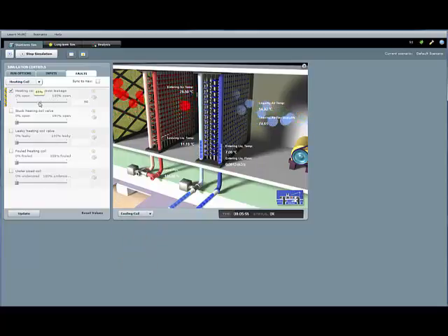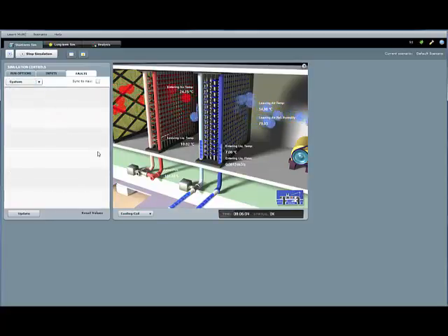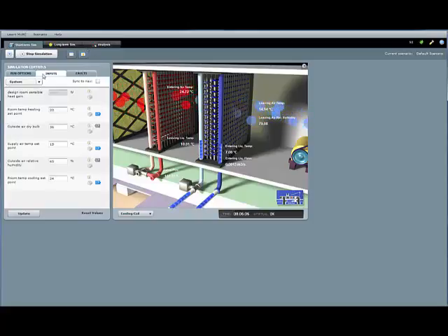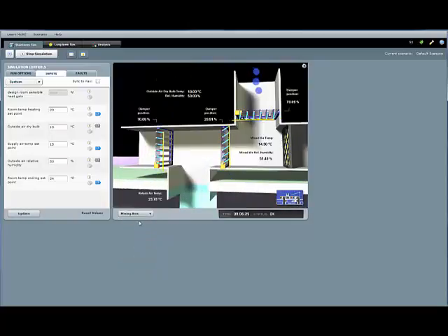We're removing the fault now, and we're going to go to our system level again, and instead of having a cooling condition, we're going to take the temperature of the outside air down to 10 or 15 degrees to show you a free cooling situation where you can actually have air coming in at around 15 degrees. You don't need to cool it at all. You just bring it in through the system and bring it into the space, and that's what's occurring here.